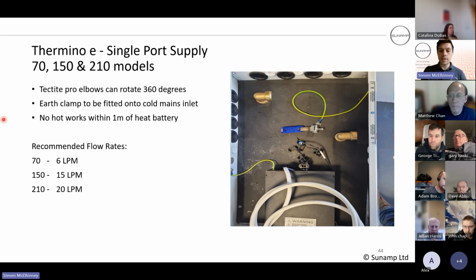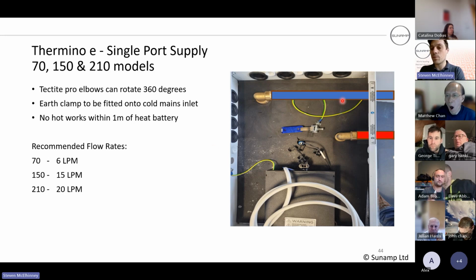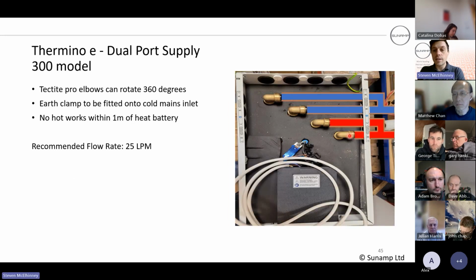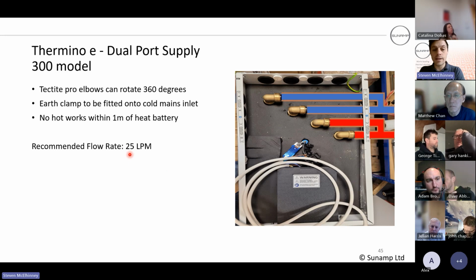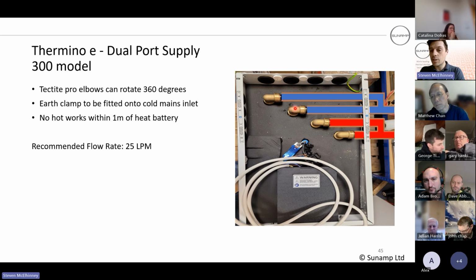I think someone mentioned about the 300s. So yeah, and obviously you've got your inlet pipe and your outlet pipe there. So inlet pipe, cold water is A, outlet on D, hot water. For the 300, they'll always come as a dual port, so 4 pipe connections. You can get up to a 25 litre per minute flow rate, but what you do is basically convert these 2 ports to a single port, as you see here. So that's like a branch, and you're basically just twinning the inlet points to the heat exchangers, and you're twinning the outlet point of the heat exchanger as well, and converting that to a single port.